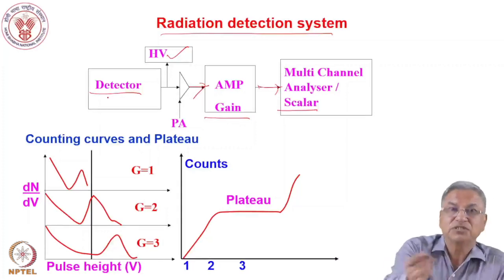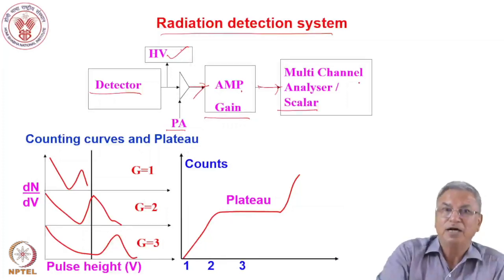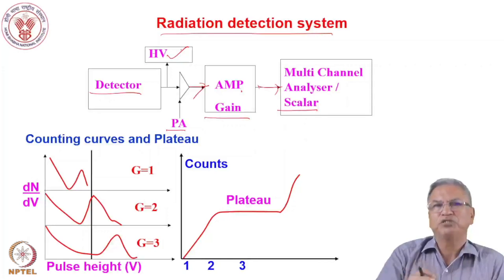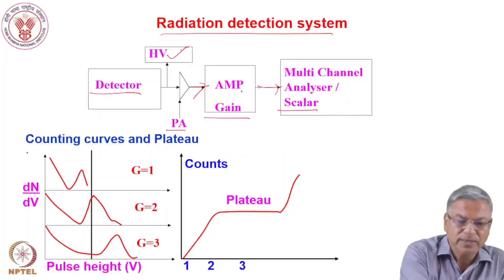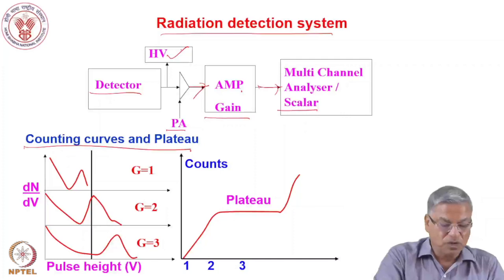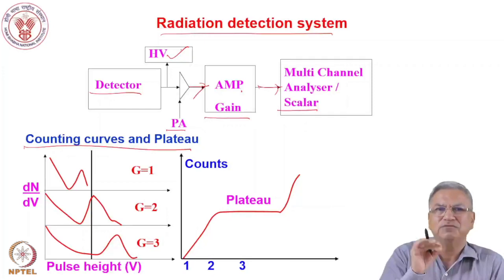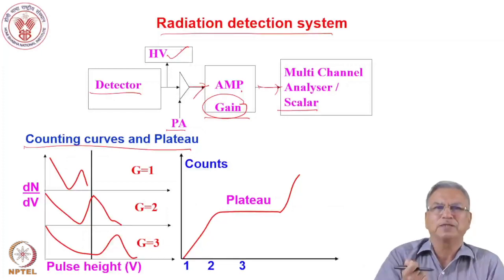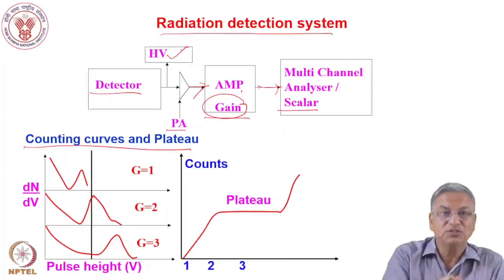Whenever we set up a detector system, we must ensure the detector is functioning in a stable manner and the settings are proper. That is why we need to generate counting curves and plateaus. Counting curve and plateau means the detector is giving you proper results. There is a quantity called gain — the amplification factor. The extent of amplification must ensure you are counting the signal and not the noise.